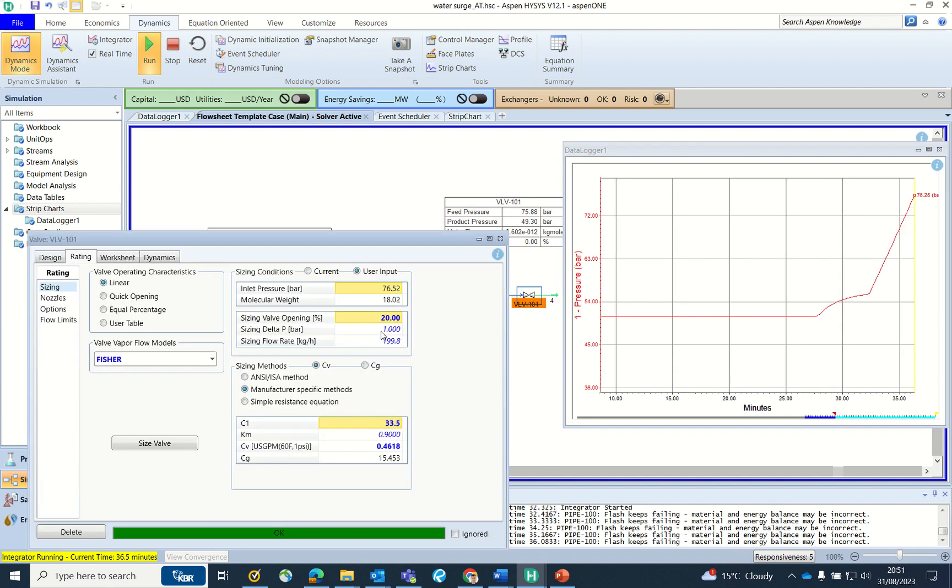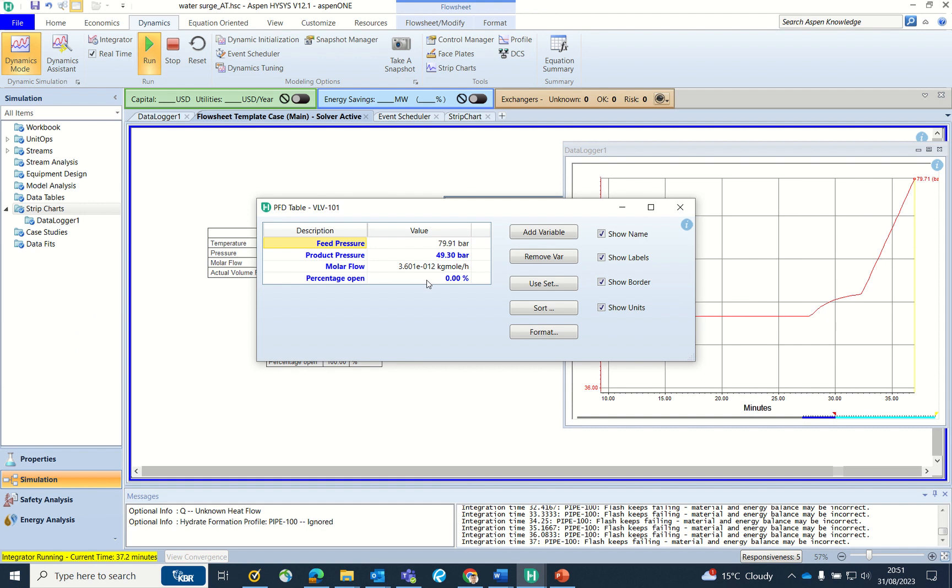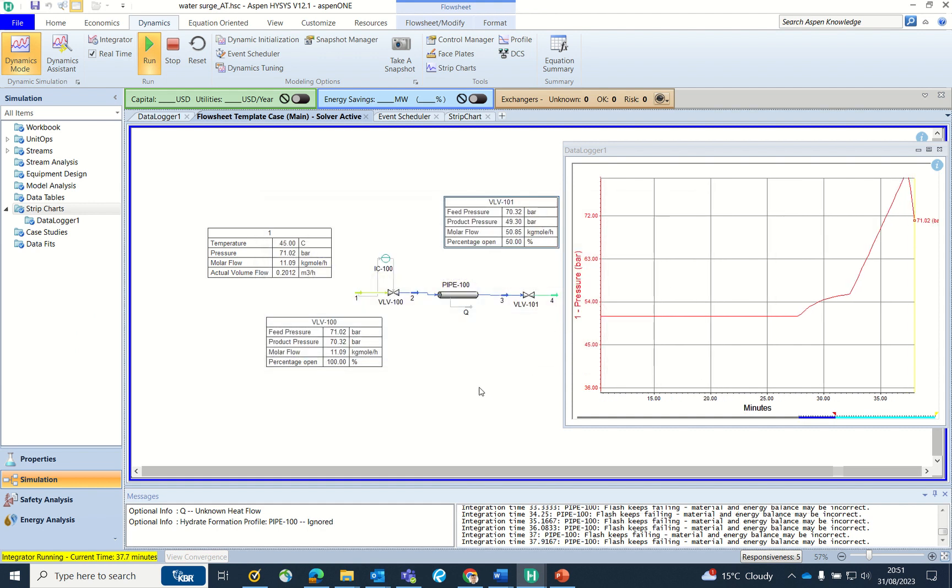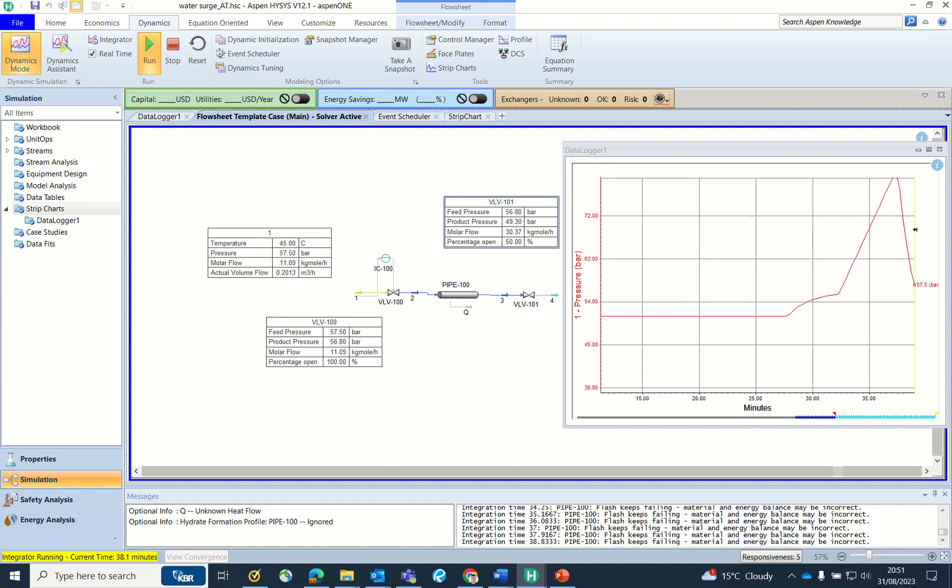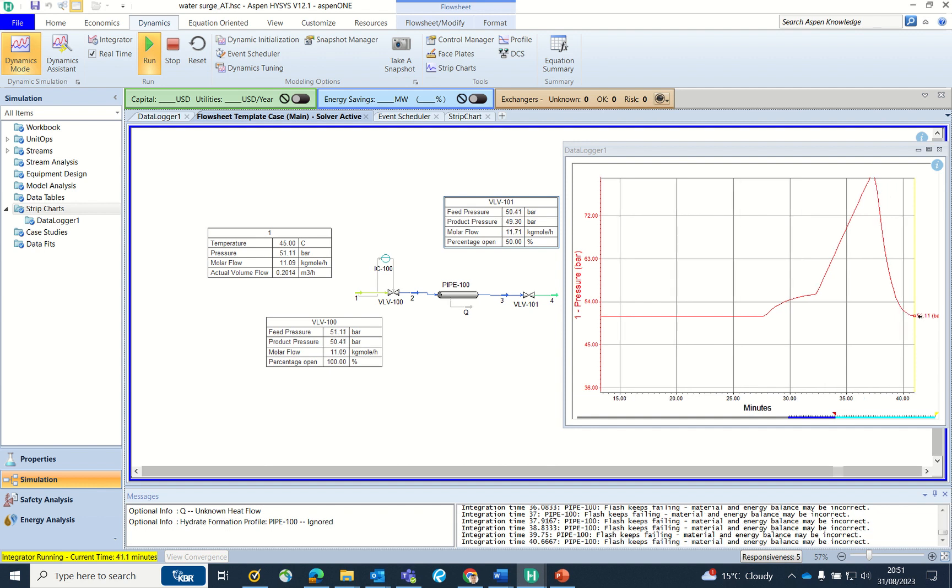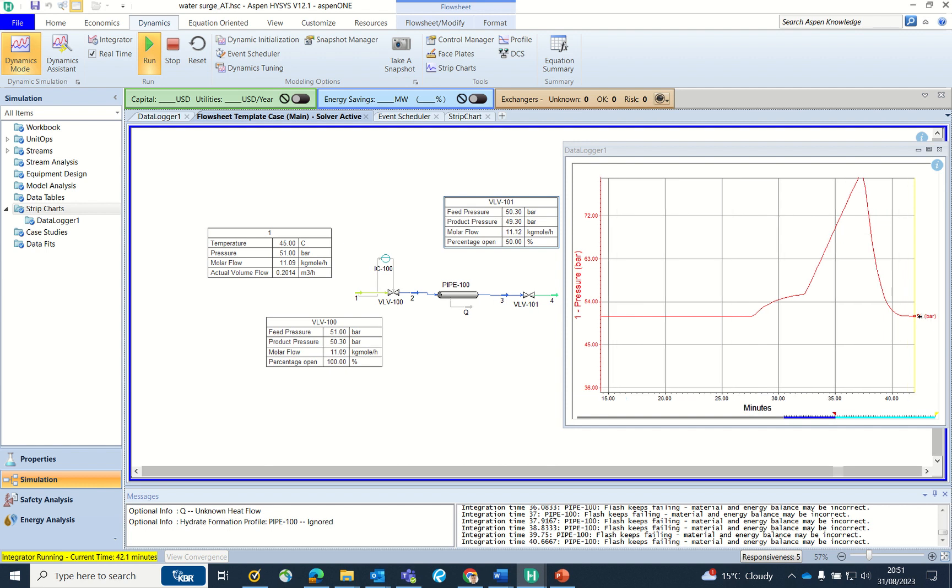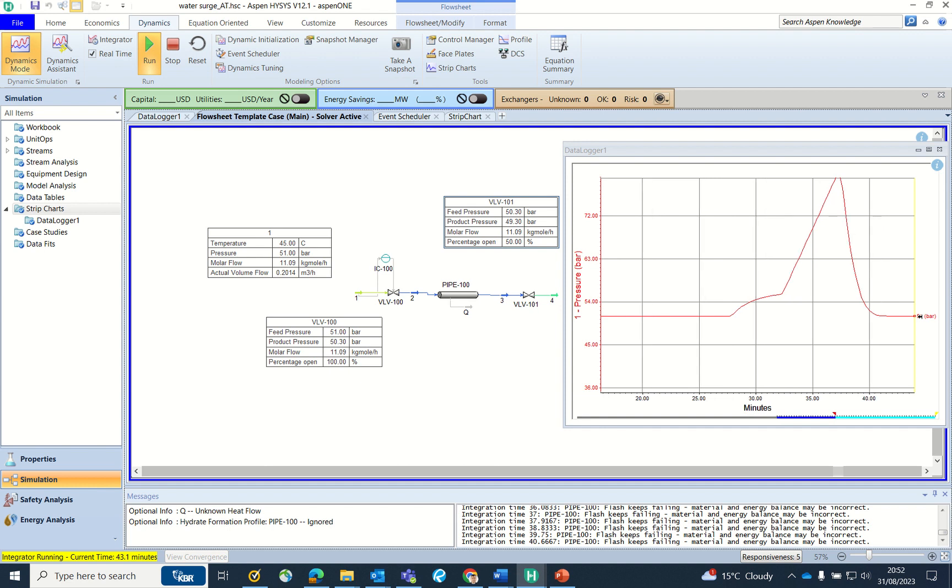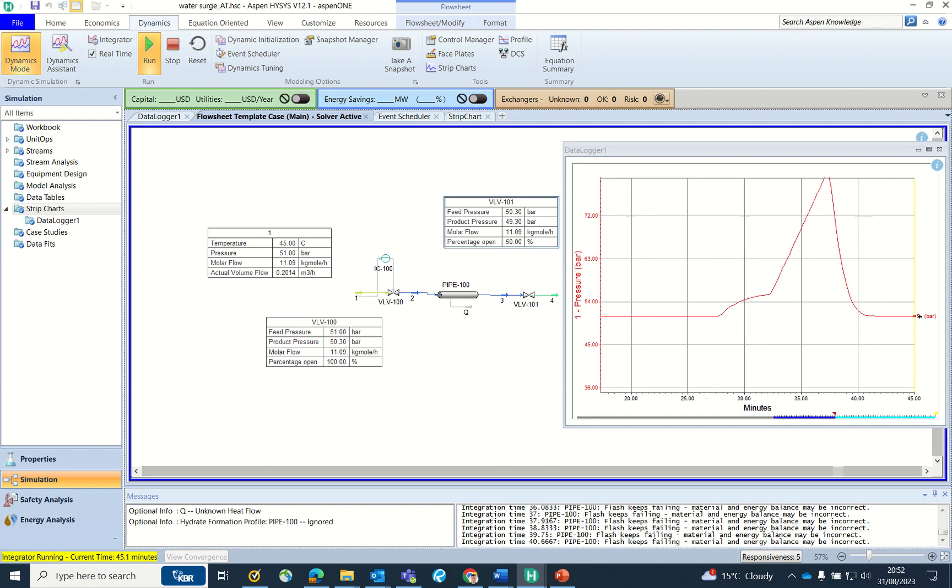Now I will open the valve to 50% and you see the drop in the pressure from 71, it's coming down back to 51 bar gauge. The idea of this video is to understand how the surge happens in the pipeline, what is the rise in the pressure, and as a process engineer you should have to define whether the PSV is required on the line or not required in the line.